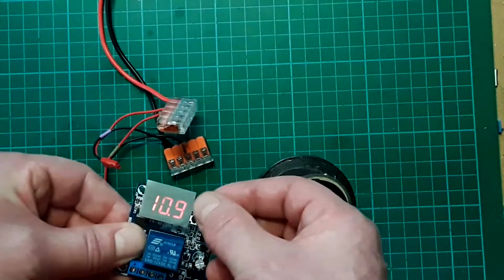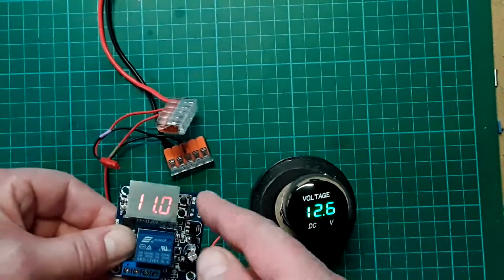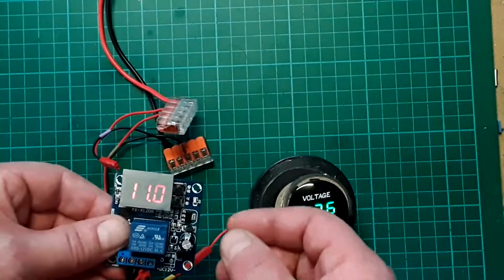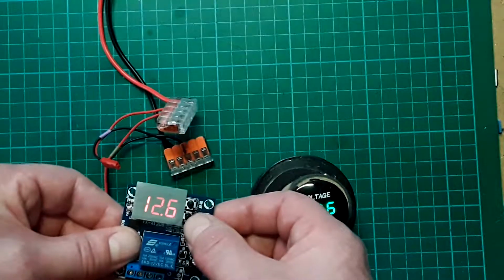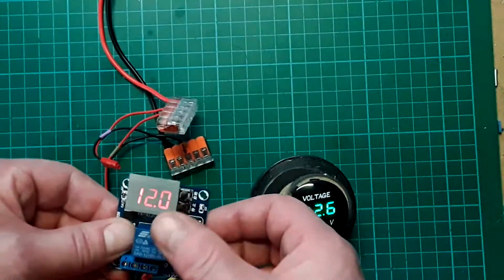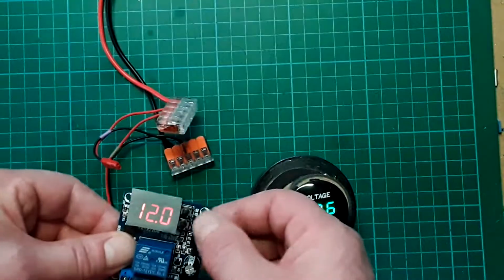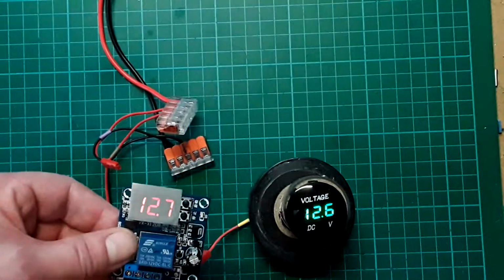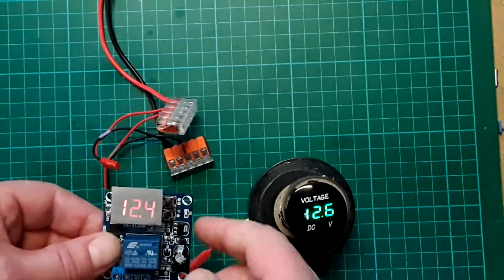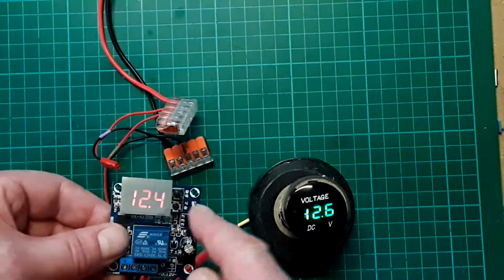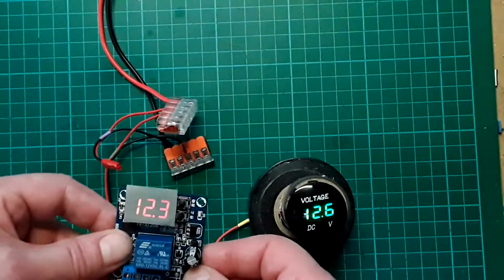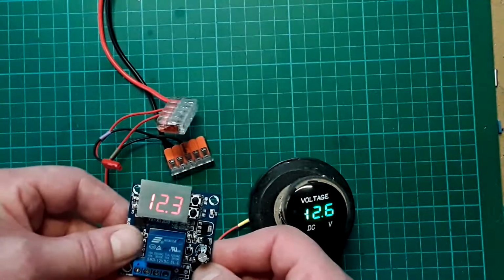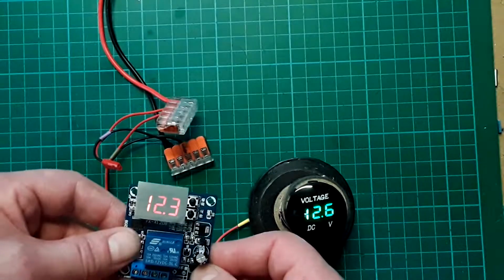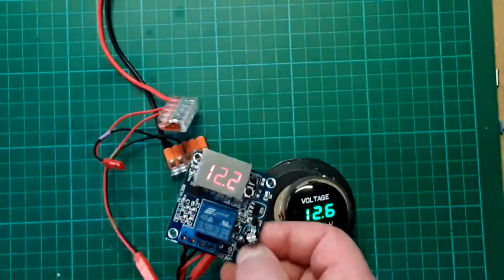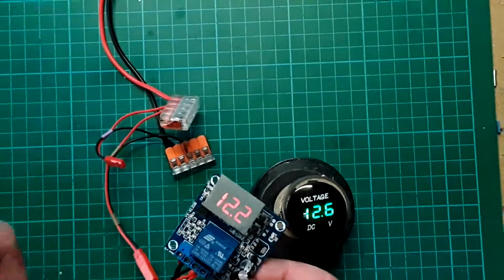I'm keeping this at 11 volts for the purpose of this demonstration. Likewise, the upper voltage is set for 12. If we want to change that, we'd hold it, go up and down, and let it time out, going back to the display voltage. So we're at 12.4 volts, between 11 and 12 — no, sorry, that's above 12, which is the voltage at which it turns back on.